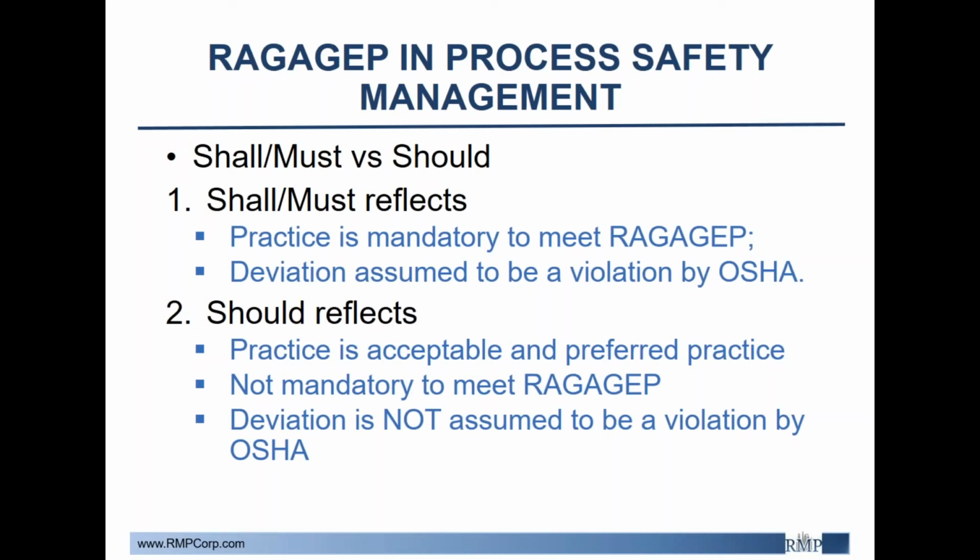Should wording reflects that a practice is acceptable and preferred practice. However, it is not mandatory to meet RAGAGEP. However, deviation from should or should not means that an employer still needs to document how their practices meet RAGAGEP. So you can do something else, but you need to show clearly that you are still meeting RAGAGEP. As such, deviation is not assumed to be a violation by OSHA, provided that the required documentation and explanation is present.